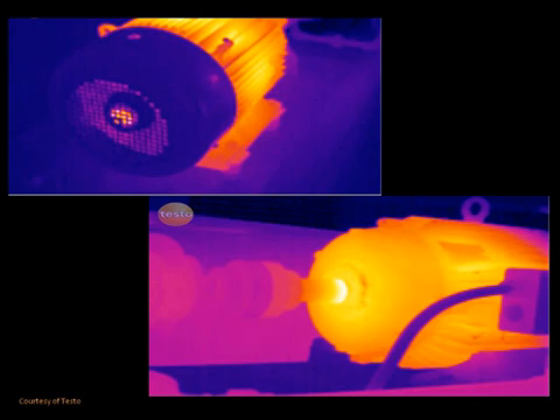Here we have two thermograms of electric motors. Notice in the lower image there is a bright white coloring on the rotating shaft. This area has a higher temperature than the surrounding components and can be an indication of shaft misalignment or a worn bearing. Further diagnostics are needed in order to identify the problem. However, thermal imaging allows us to view these systems while under full operating load, and the systems do not have to be shut down or taken offline for us to conduct an inspection. This allows us to detect potential problems before there is a breakdown, which can result in thousands of dollars worth of lost man-hours in the event of an unexpected failure.